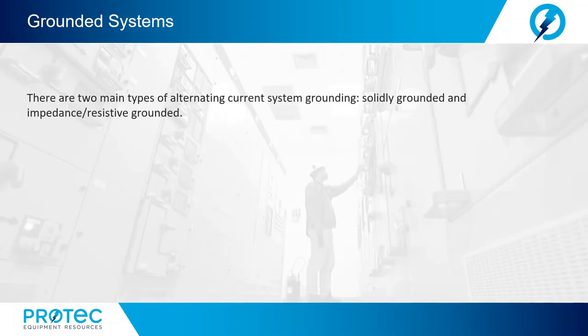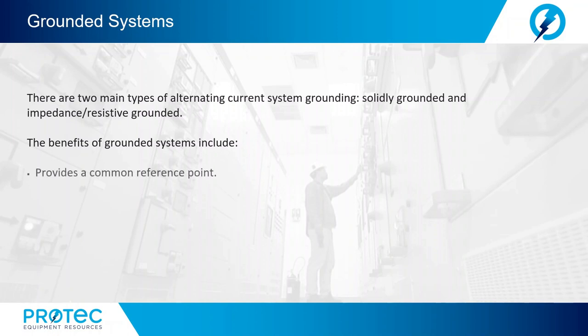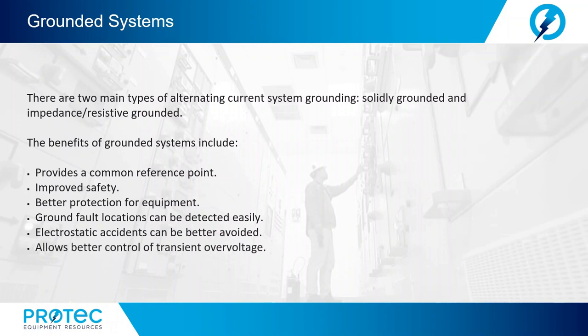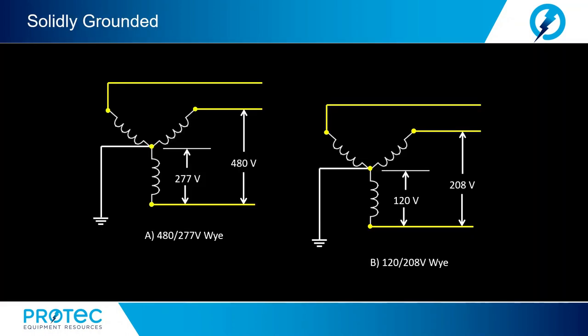There are two main types of AC system grounding: solidly grounded systems and impedance or resistive grounded systems. The benefits of grounded systems include providing a common reference point, improved safety, better protection for equipment, relatively easy ground fault location detection, better avoidance of electrostatic accidents, and better control of transient overvoltage.